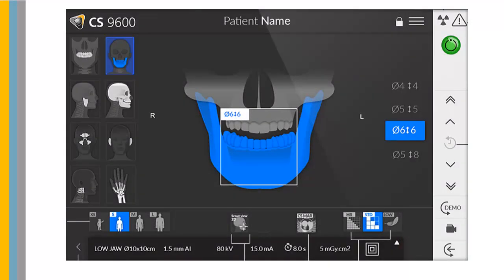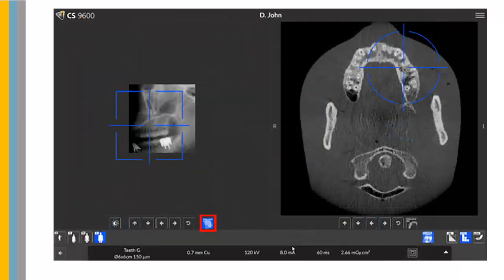Additional functions on the 3D control panel include Standard, low, or high resolution imaging mode. There are two functions used to evaluate or change the field of view position for an acquired image. Scout View 2D is used to acquire a single sagittal slice view to determine that the area for an exam is positioned correctly. Smart Auto 3D is an optional feature which recommends the patient size and displays sagittal and axial slice views to determine the area for an exam is positioned correctly.